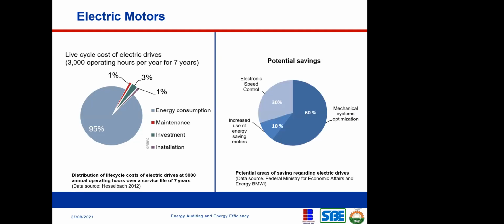Now, like I said earlier, 60% saving can be achieved from mechanical system optimization. Mechanical system optimization means the motor-driven applications, not the motor itself. If you optimize your mechanical system, then you can rightly size your motor so that you don't oversize it. Sometimes you're operating motors at a very low load factor, which means you oversized the motor, and it becomes a problem.